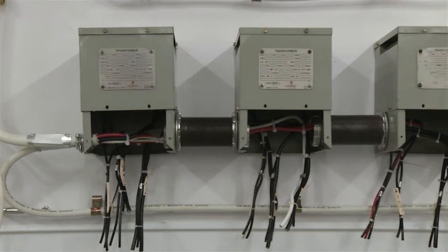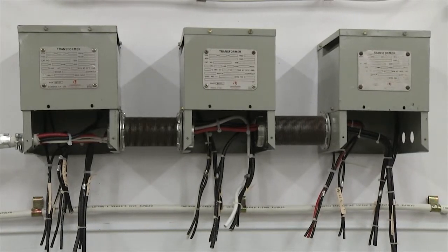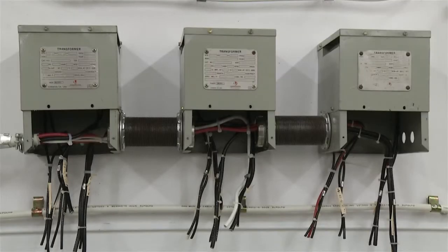Here is a typical bank of 3 transformers. In order to complete the hookup, you will need 2 nipples, 8 bushings, and 4 lock rings. They have already been installed in this video. Remember that holes may need to be drilled for these pieces if they are not already there.